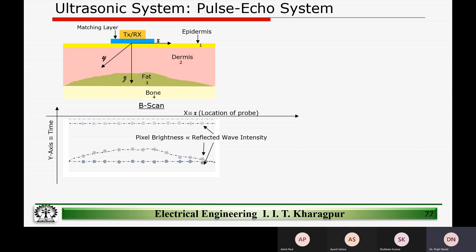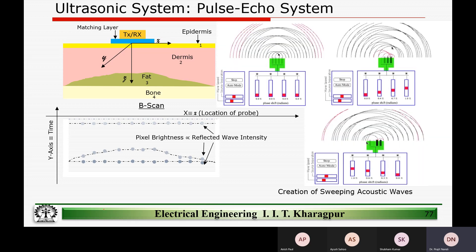This is called a B-scan. The problem with B-scan is that physically moving the ultrasound transducer along the body causes friction and is very painful for the patient. To solve this, we use something called a phased array — an array of transducers used to mimic the movement of the transducer along the body.